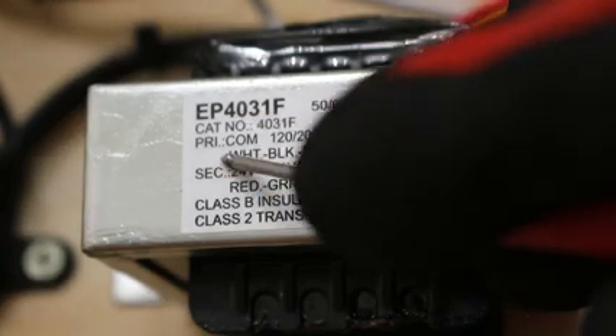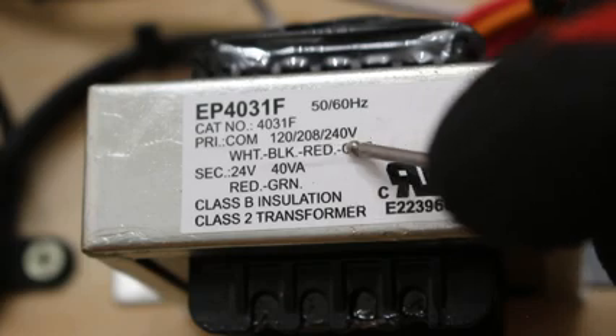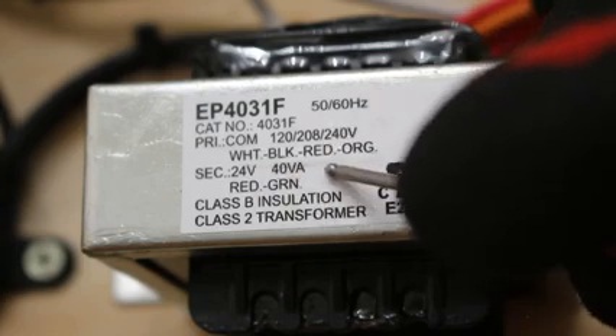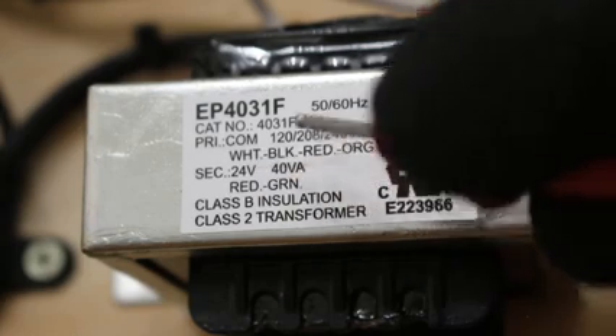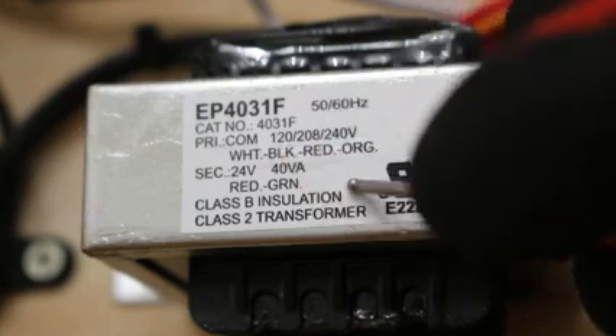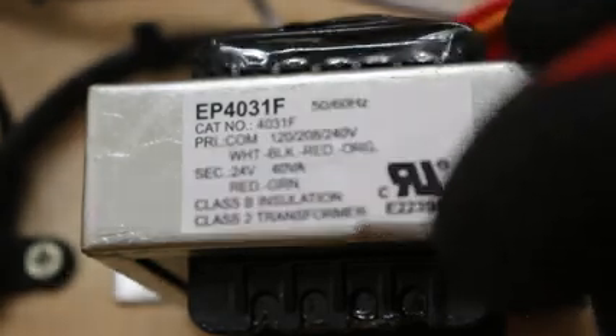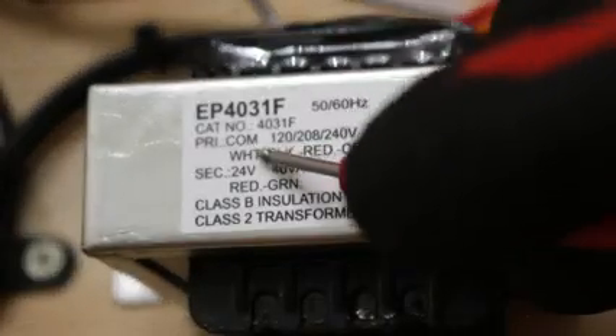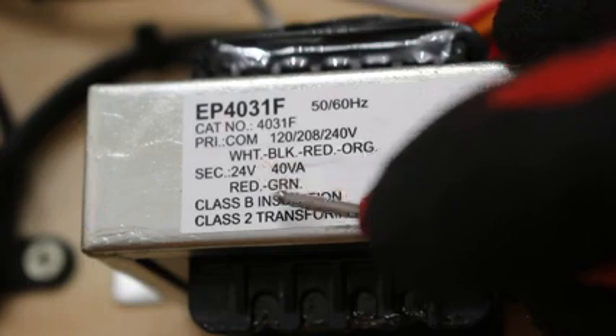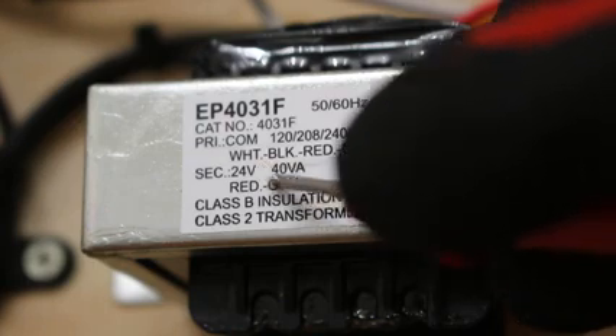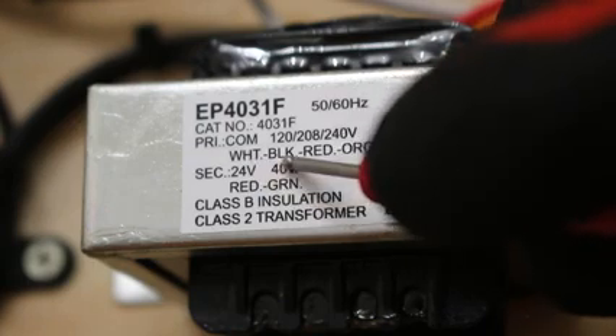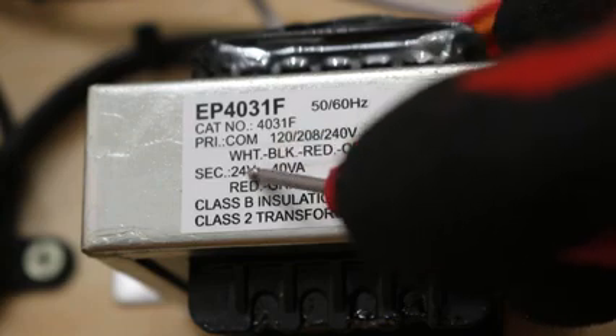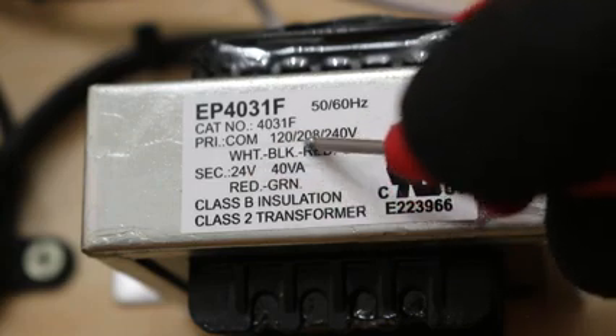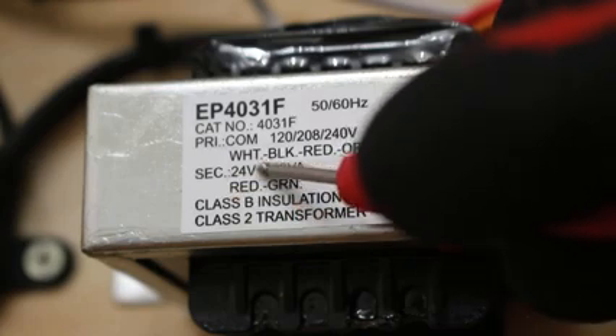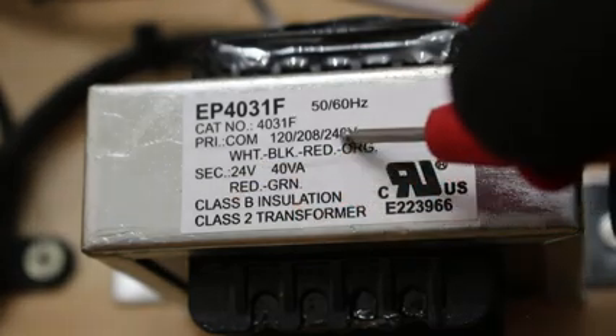But if you look at our primary, we notice we have a few multiple readings with a few multiple colors. This indicates to us that we could have any one of these voltages, but it's always going to be between two wires. One wire that's always going to be connected is your common, and that's going to be your white wire. So what is this actually telling us? That means between white and black, we should have 120. Between white and red, we should have 208. And between white and orange, we should have 240.